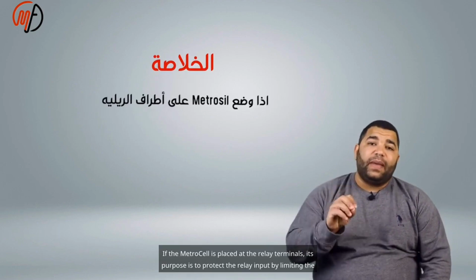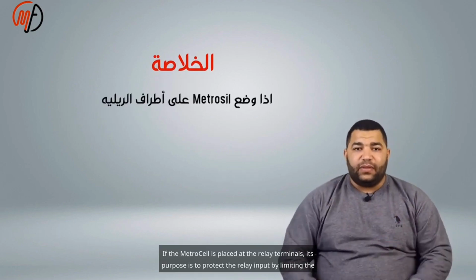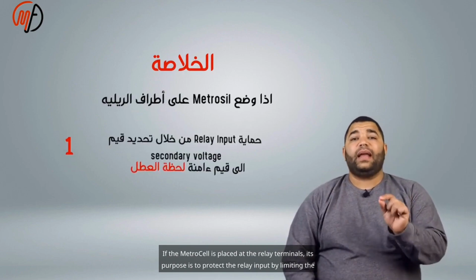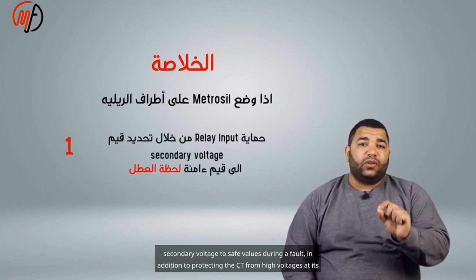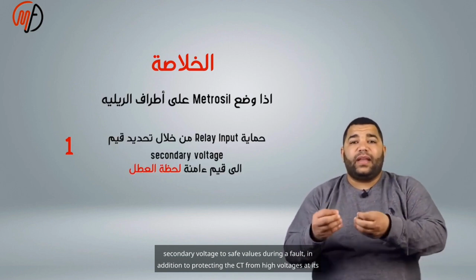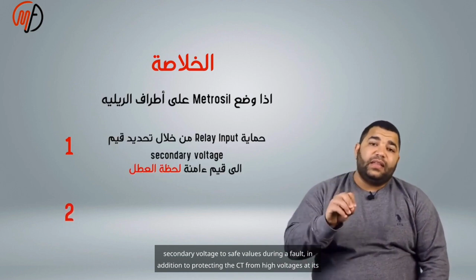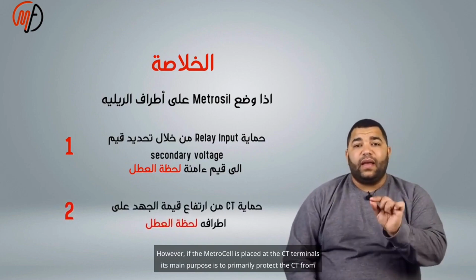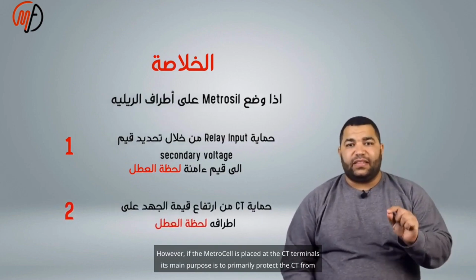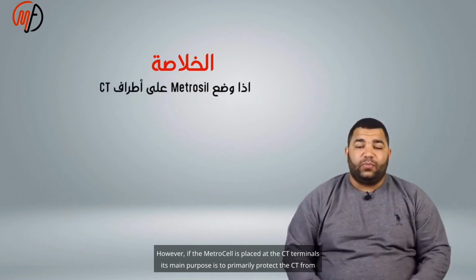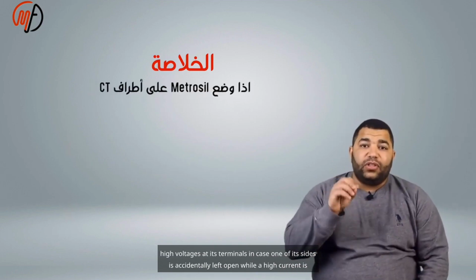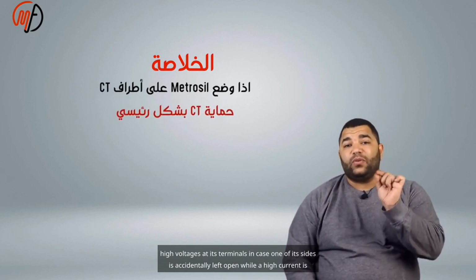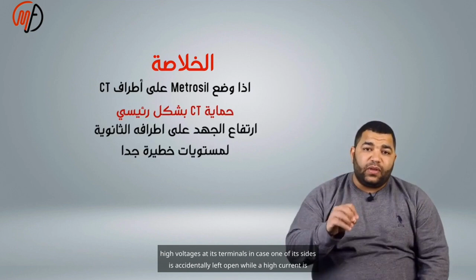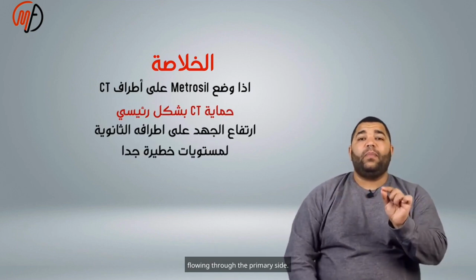If the Metrosil is placed at the relay terminals, its purpose is to protect the relay input by limiting the secondary voltage to safe values during a fault, in addition to protecting the CT from high voltages at its terminals during a fault. However, if the Metrosil is placed at the CT terminals, its main purpose is to protect the CT from high voltages at its terminals in case one of its sides is accidentally left open while a high current is flowing through the primary side.